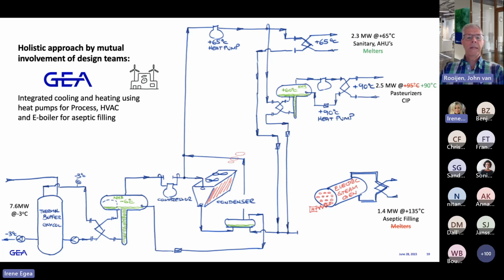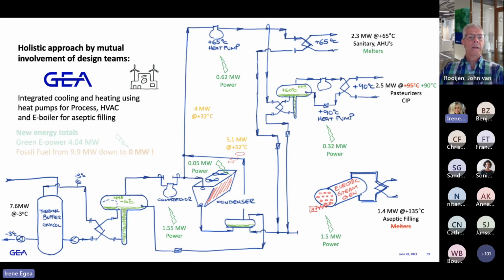Please forward. And as you can see, initially the condenser heat was about 9 megawatt. Now we take away 4 megawatt, so almost half of it, to be able to generate the heat. Still, there is an overload of heat, especially from HVAC cooling, which has to be dissipated. Please forward one animation.